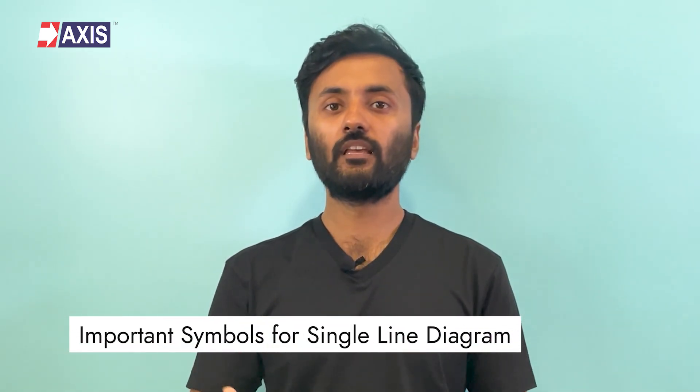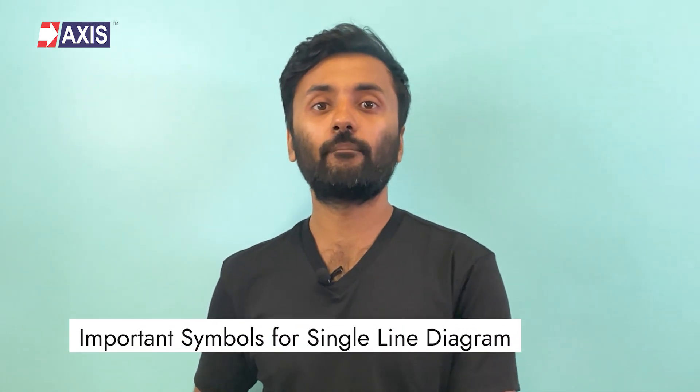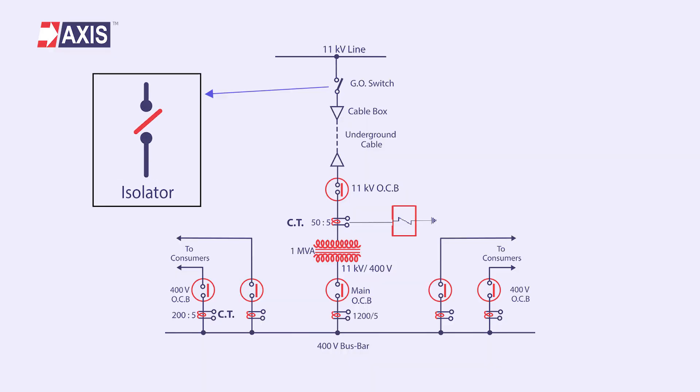Now let's look at some of the important symbols that will help you understand a single line diagram. Firstly, the isolating switch. In power substations, it is required to disconnect a part of the system for general maintenance and repairs. This is accomplished by an isolator — a switch which is designed to open a circuit under no load. For example, if the entire substation is divided into five sections, each section can be disconnected with the help of an isolator for maintenance.